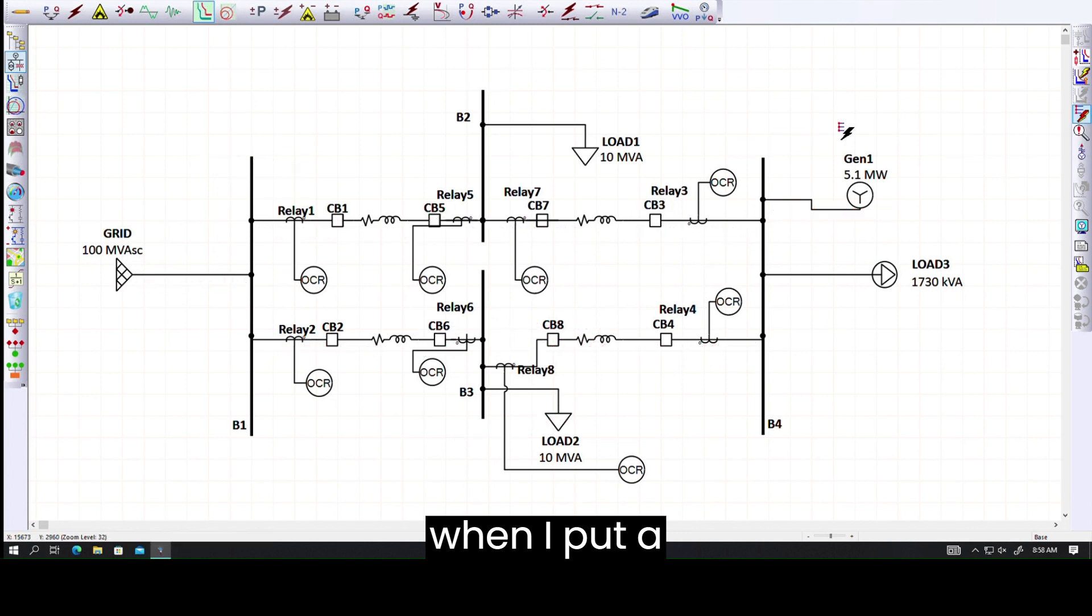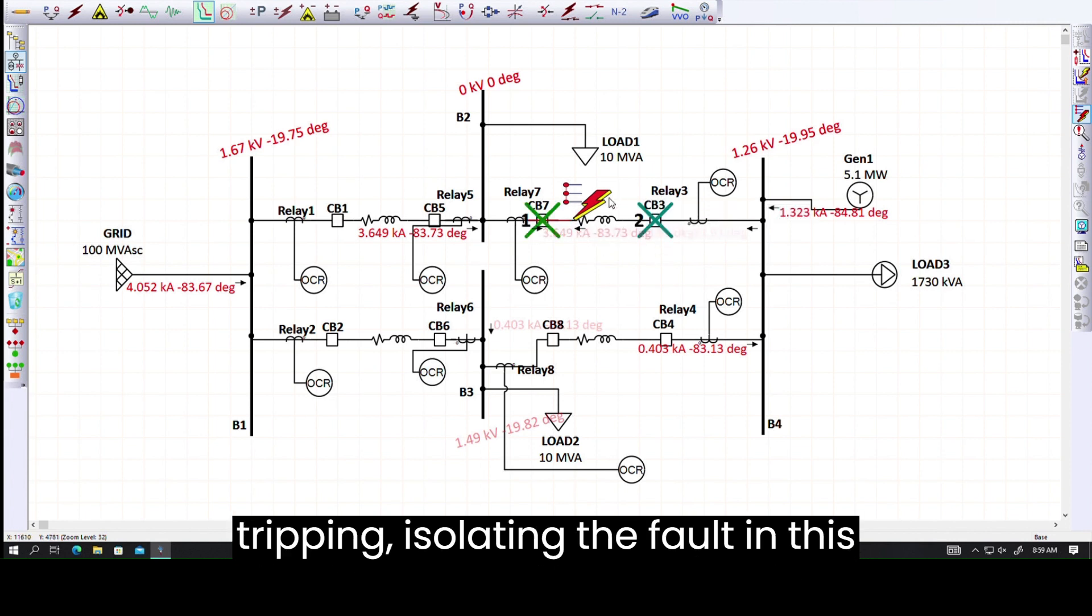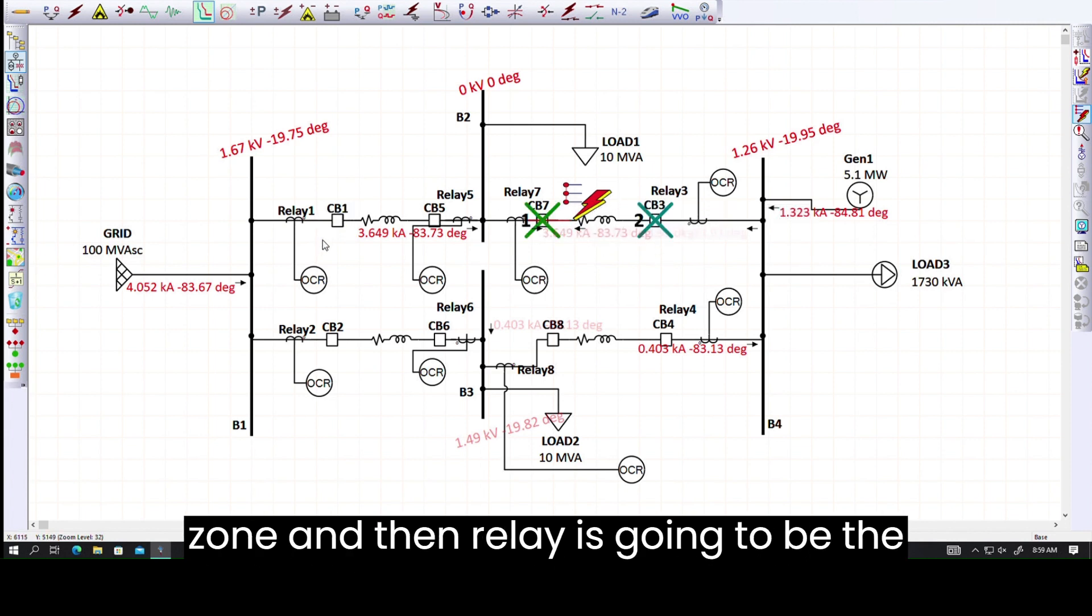Now if we want to figure out or observe the fault in between the lines, right here I have a line in between relay 7 and relay 3. When I put a fault right here, relay 7 and relay 3 are going to be tripping, isolating the fault in this zone, and then relay 1 is going to be the backup.